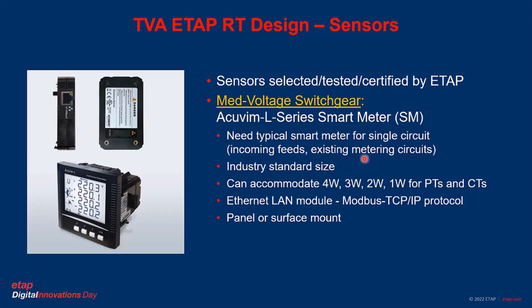These are a typical industry standard size. They're about 4-inch square. They can accommodate 4-wire, 3-wire, 2-wire, or even 1-wire systems for your PTs and CTs. They have a built-in Ethernet LAN module, which can supply Modbus TCP/IP protocol, which is compatible with the ETAP RT server, and they can be either panel or surface mounted.